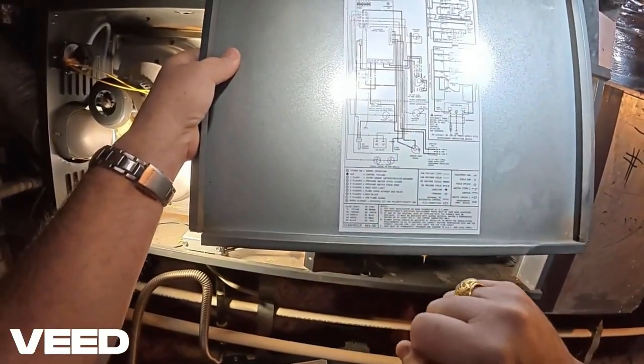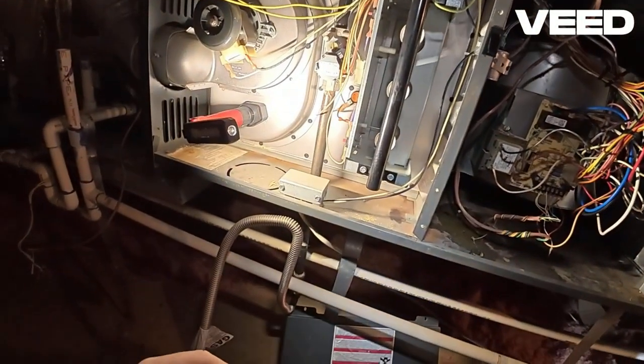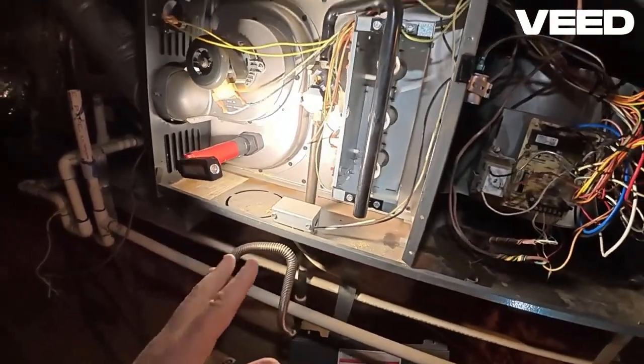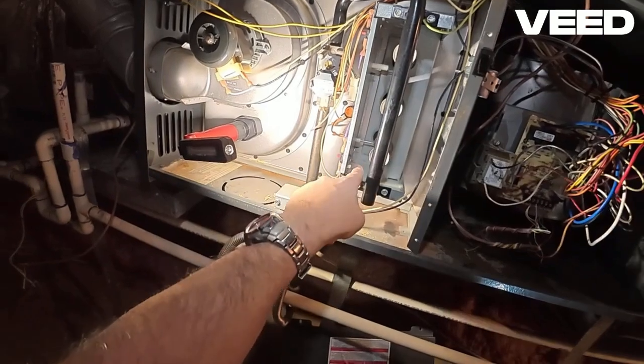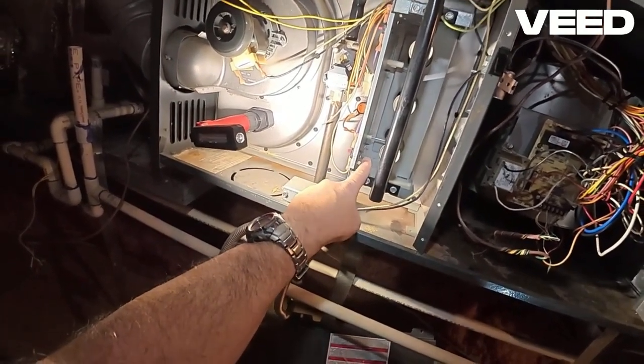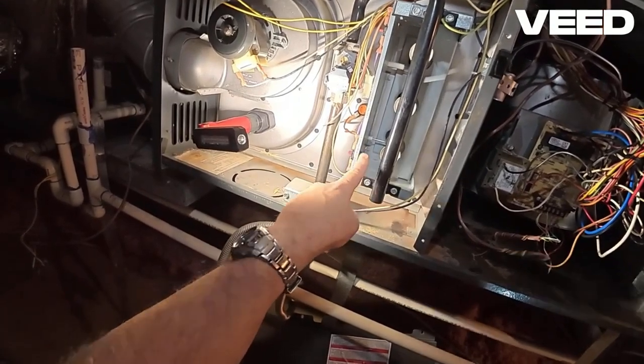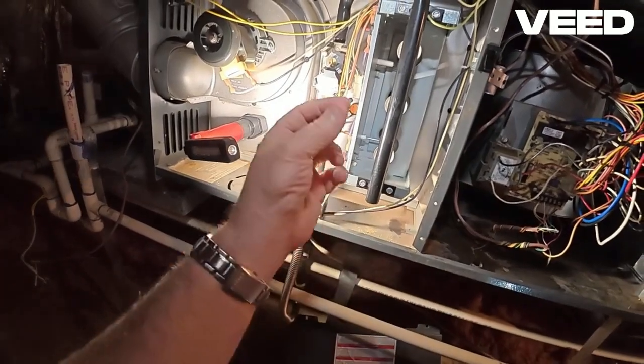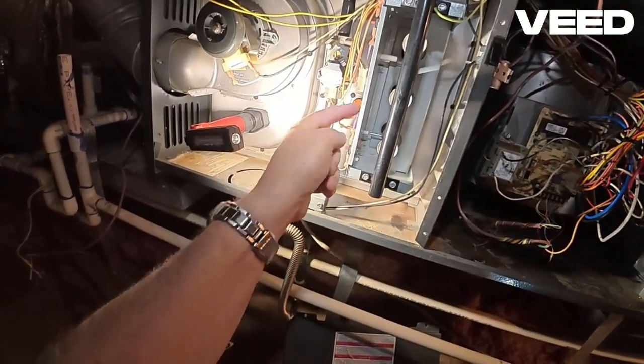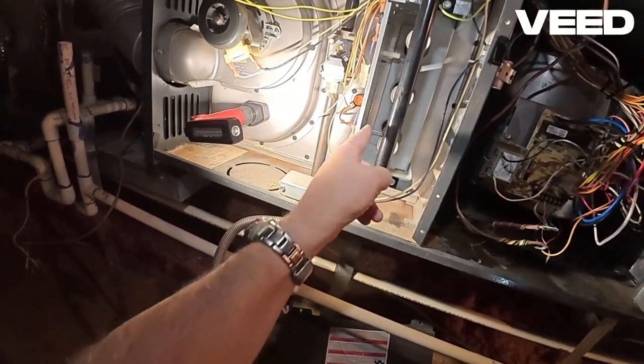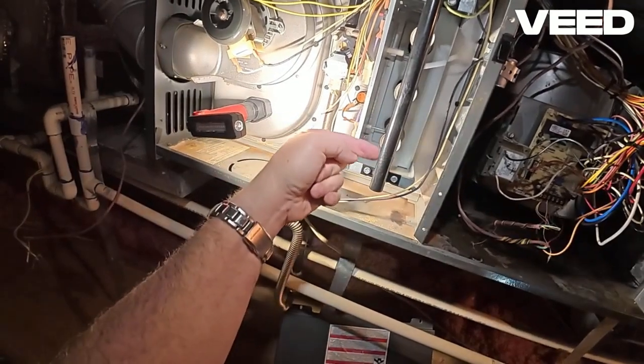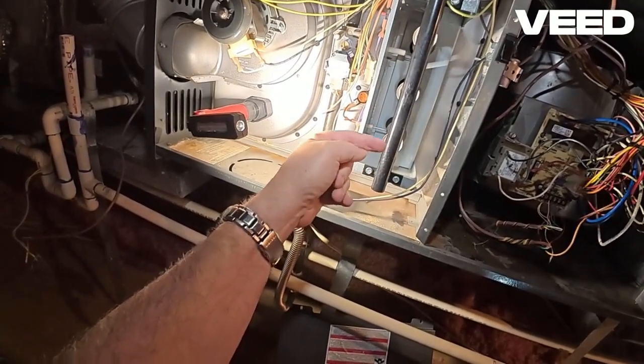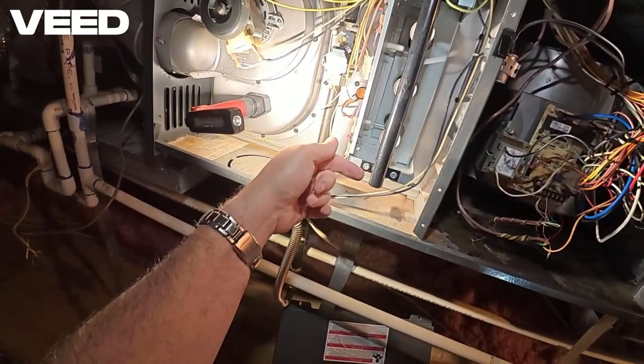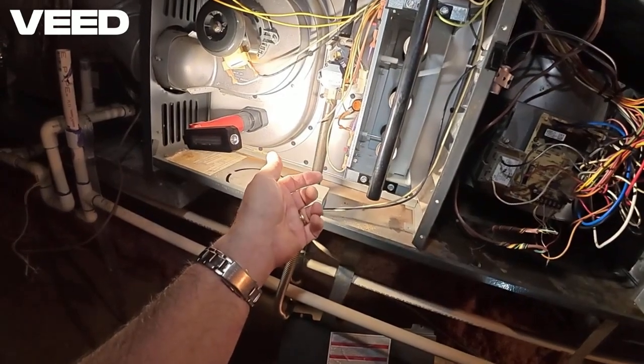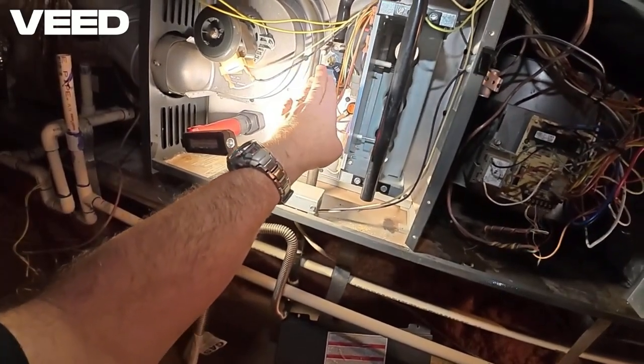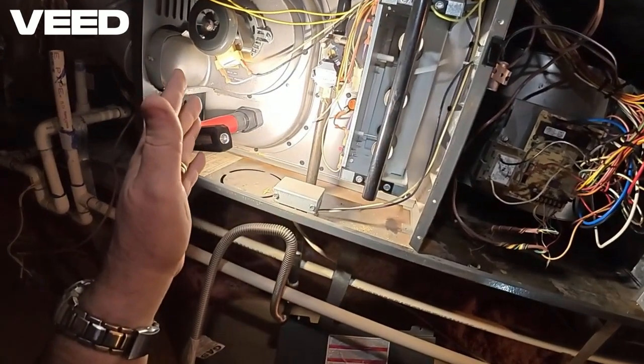The next one is a low flame signal. So we talked about this one a bit, and I have other videos on this as well, but this again is our flame sensor here at the bottom, and it senses flame and it sends a signal back to the control board that we do indeed have flame. If this is dirty with carbon, so this is in the flame all the time, and it's a piece of metal, and if that gets dirty with carbon, a buildup on it, it won't sense the flame, and it will not allow the system to operate.